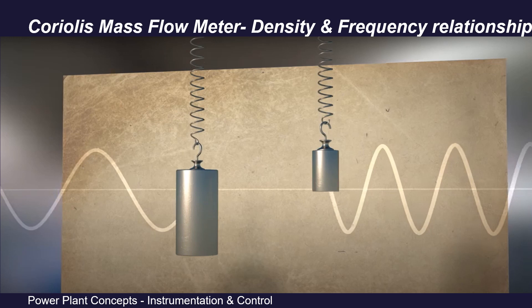We know the stiffness of the flow meter remains essentially constant, so the mass and density of the fluid contained in the fixed volume of the flow tube is the only variable affecting the frequency. Volumetric flow can also be derived from mass flow measurement — because we know the mass and the density, mass flow divided by density gives us the volumetric flow. Thus Coriolis mass flow meters provide highly accurate direct mass flow measurement.